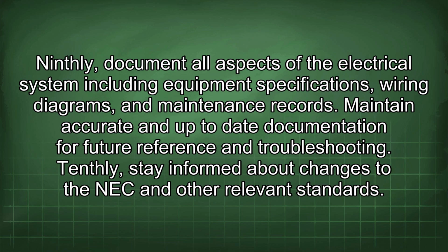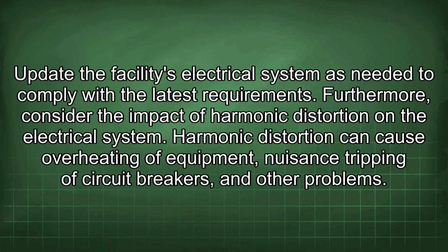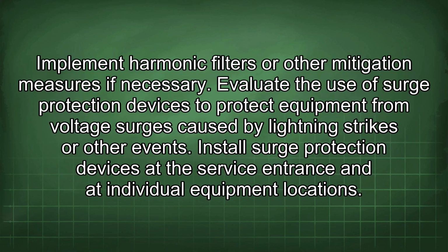Tenthly, stay informed about changes to the NEC and other relevant standards. Update the facility's electrical system as needed to comply with the latest requirements. Furthermore, consider the impact of harmonic distortion on the electrical system. Harmonic distortion can cause overheating of equipment, nuisance tripping of circuit breakers, and other problems. Implement harmonic filters or other mitigation measures if necessary.